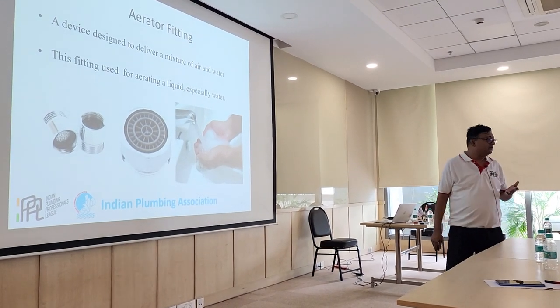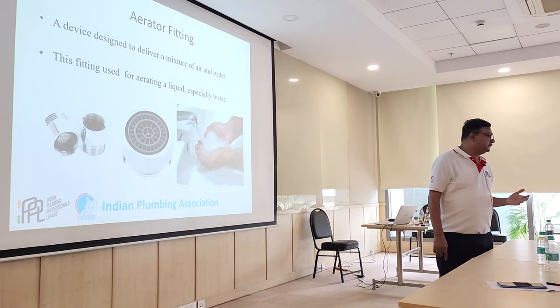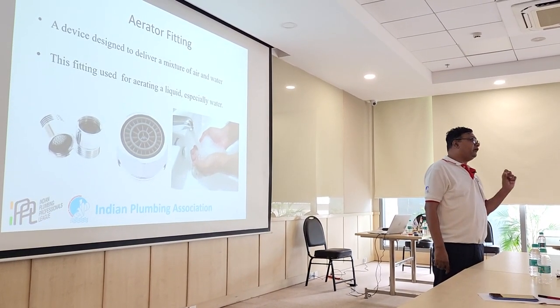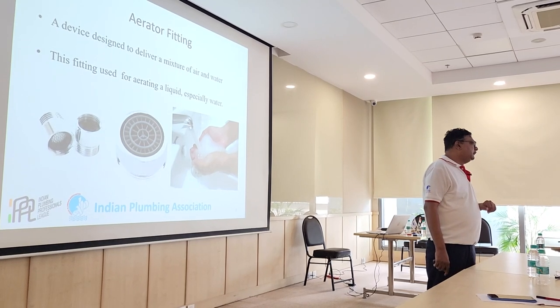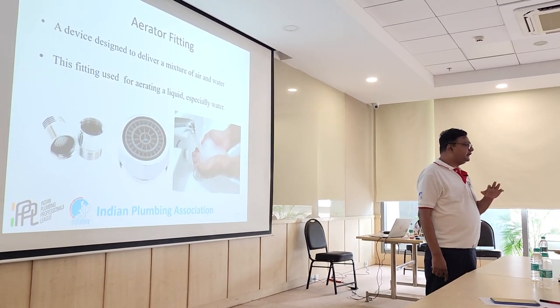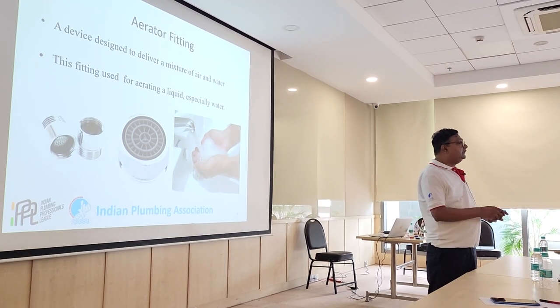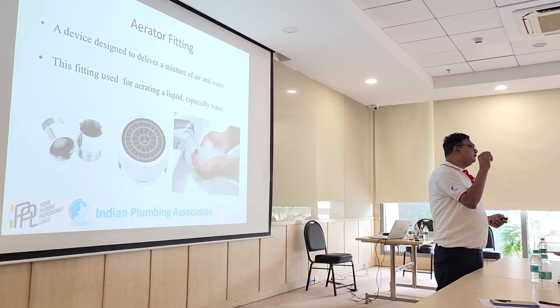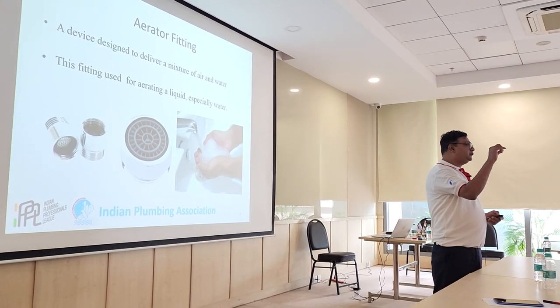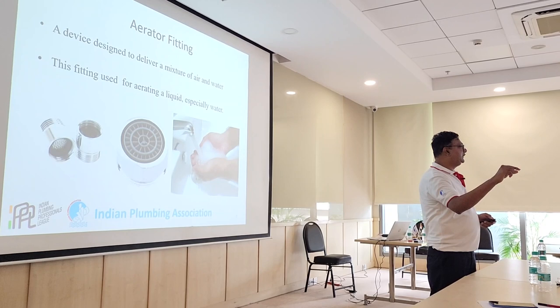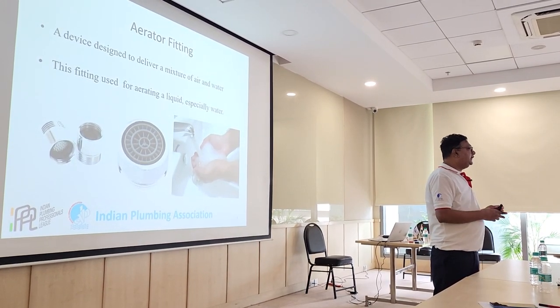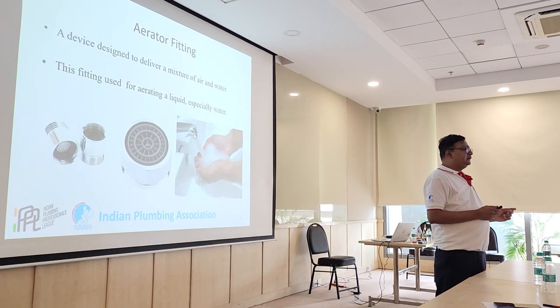If you go to the LEED or IGBC certifications, there are different types of aerators available based on what type of certification you are doing — whether silver, gold, platinum, or just compliant. There is a specific type of aerator suggested in the code. The aerator should reduce the flow by 5%, 10%, 25%, or 50%, and that gives you the points.